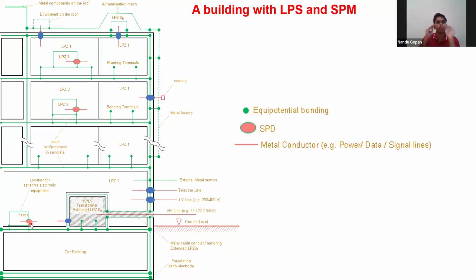So this is a proper LPS and SPM requirement. If you are asking how lightning protection is done here: they have put an air termination mesh, so air termination is done. For the down conductor, they have used the steel reinforcement as the down conductor, so that is done. Next, they have connected the foundation earth electrode, so earthing is also done. Equipotential bonding is also done, so internal LPS is also done. So LPS - external and internal - is done.